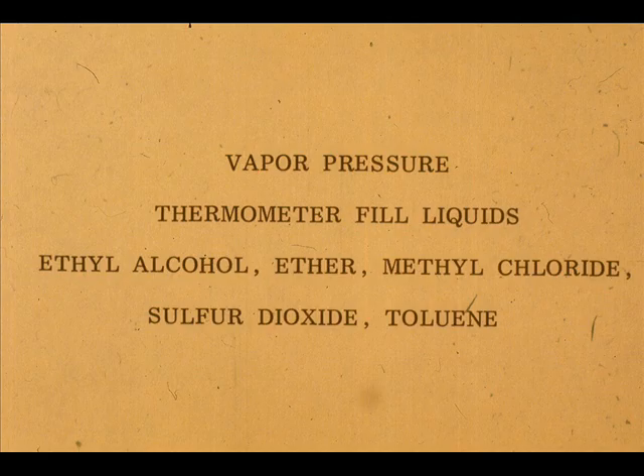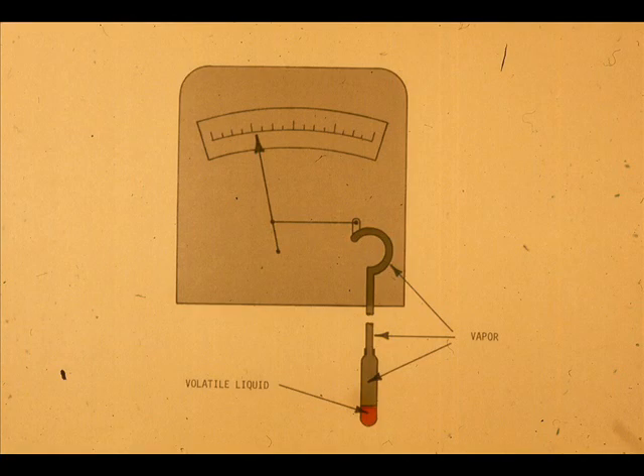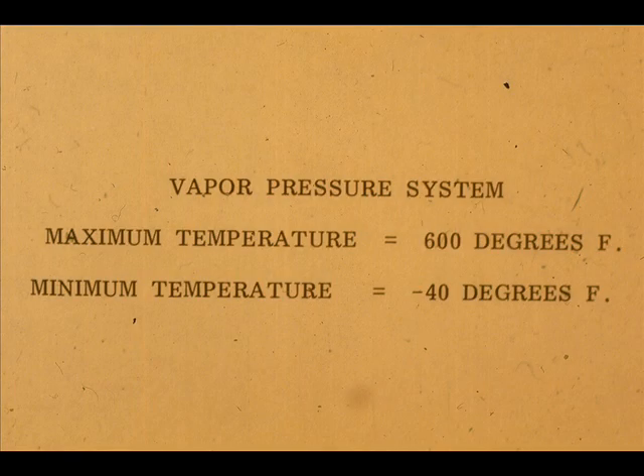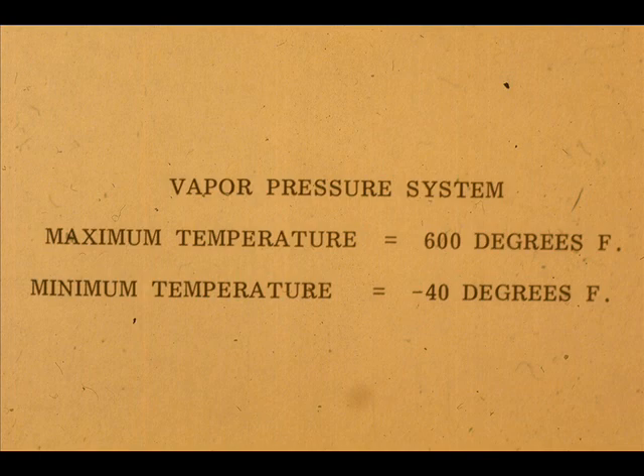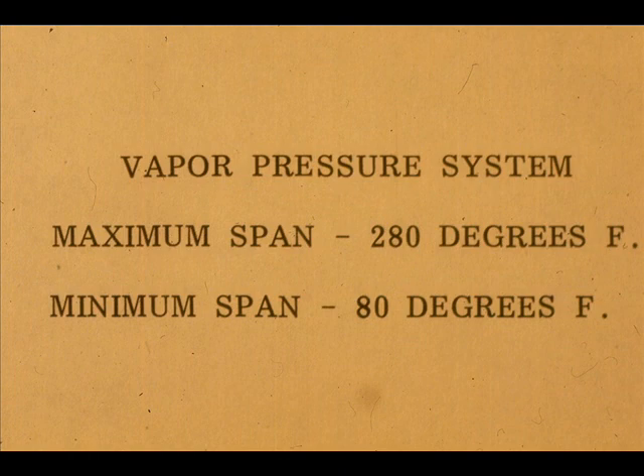The most common liquids used for thermometer fills are ethyl alcohol, ether, methyl chloride, sulfur dioxide, and toluene. The amount of liquid used depends on the range desired and the temperatures to which the bulb will be exposed. The maximum operating temperature is 600 degrees Fahrenheit. The minimum temperature is minus 40 degrees Fahrenheit. The span can be a maximum of 280 degrees Fahrenheit and a minimum of 80 degrees Fahrenheit.